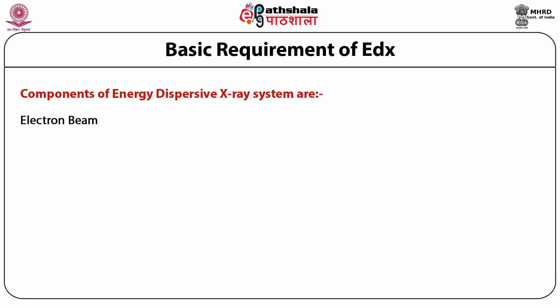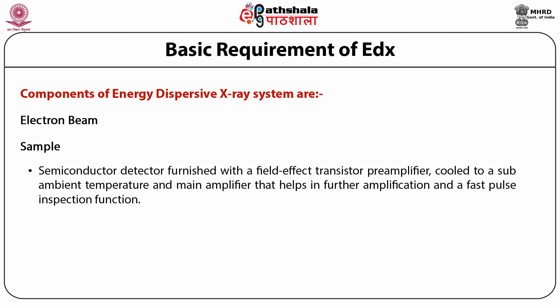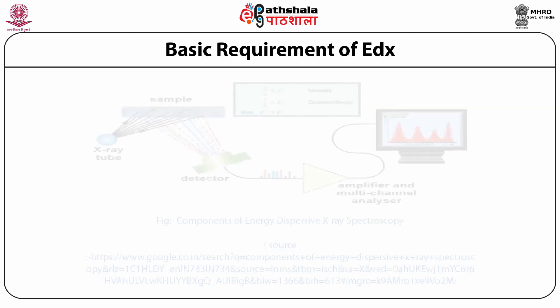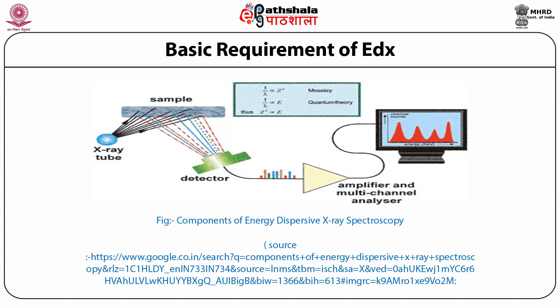The basic requirements of EDX include: an electron beam, the sample, a multi-channel analyzer, a semiconductor detector furnished with a field-effect transistor pre-amplifier cooled to sub-ambient temperature, and a main amplifier that helps in further amplification and fast pulse inspection. All these parts are controlled with a computer-assisted system like a multi-channel analyzer (MCA) or a computer-assisted x-ray analyzer (CXA). The diagram shows the x-ray tube, x-rays falling on the sample, reaching the detector, moving to the amplifier, and finally displaying results on the computer screen.